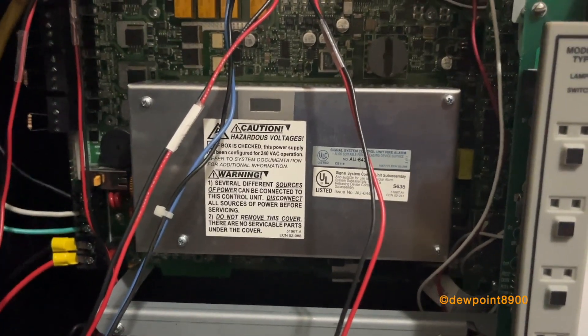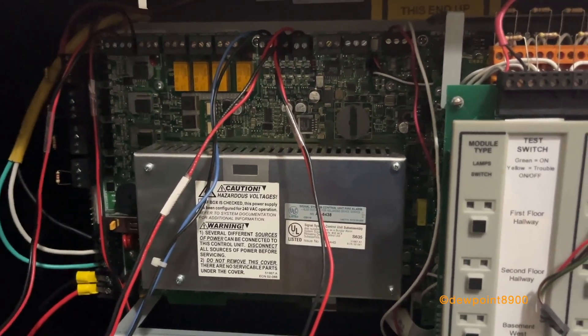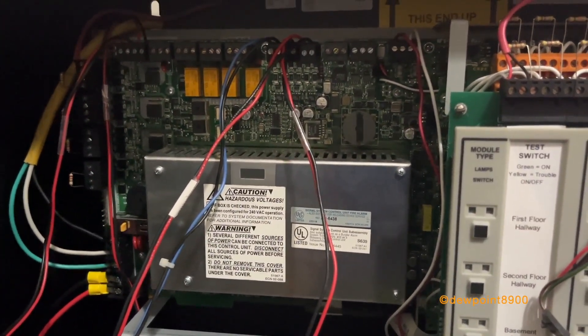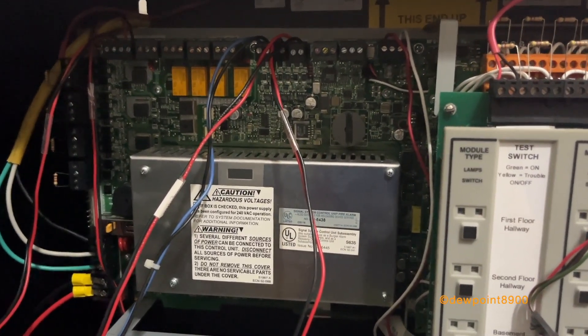Panel circuit modules connect via ribbon cable to two connectors on the bottom of the CPU. There's a longer connector for the KTM-2 keypad display module, which is the main display for the NFS-640. It allows for viewing, controlling, and programming the system from the front panel. All ONYX series panels can operate without any display at all, especially on network systems where they may be controlled by an NCA or a network command center elsewhere in the system. In such cases, the only way to program these panels is through the Veri-Fire Tools software.